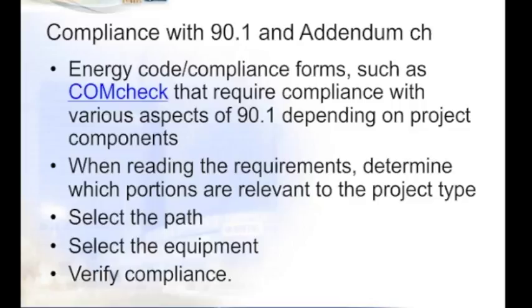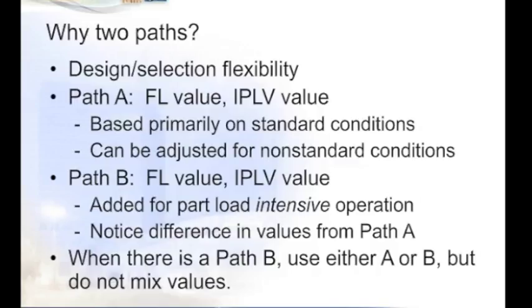So why are there two paths to begin with? When the standard was first written, they just listed the efficiencies that you needed to meet. As things went along, the ASHRAE folks and the committees decided that there's more than one way to skin a cat, so to speak. So two different paths. One, primarily path A, is based on standard conditions. They can still be adjusted, but the path was for both full load and part load values. Path B also has both full and part load values, but the path was added to 90.1 in the 2010 version for part load intensive operation, whereas you weren't operating your equipment primarily at full load. This one allowed for more efficient operation of the equipment.